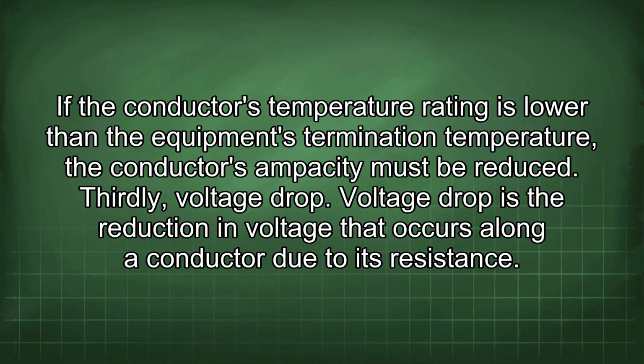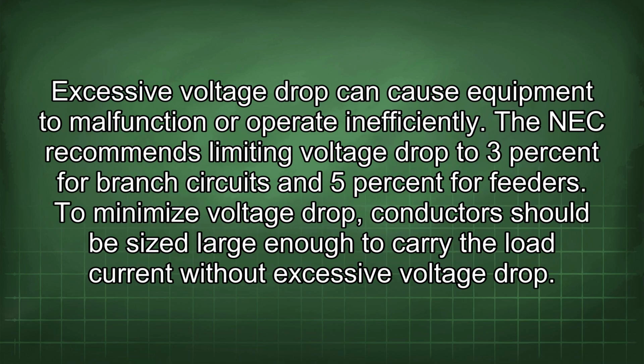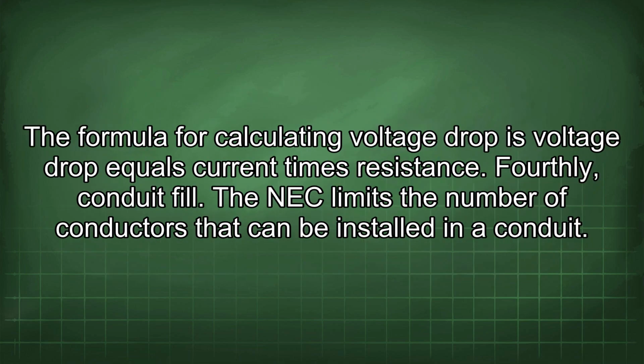Thirdly, voltage drop. Voltage drop is the reduction in voltage that occurs along a conductor due to its resistance. Excessive voltage drop can cause equipment to malfunction or operate inefficiently. The NEC recommends limiting voltage drop to 3% for branch circuits and 5% for feeders. To minimize voltage drop, conductors should be sized large enough to carry the load current without excessive voltage drop. The formula for calculating voltage drop is voltage drop equals current times resistance.